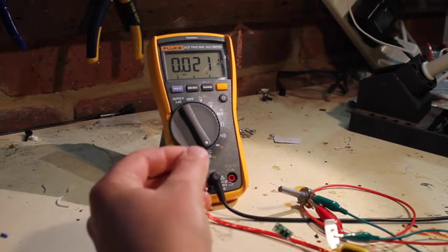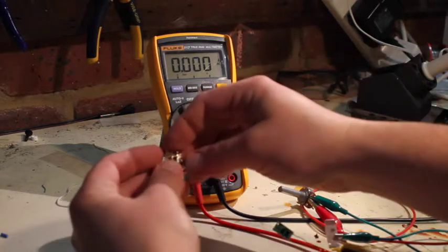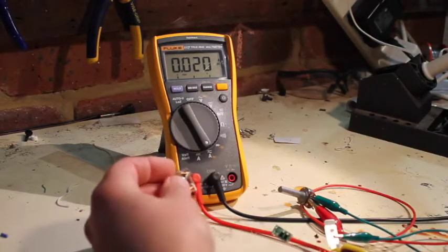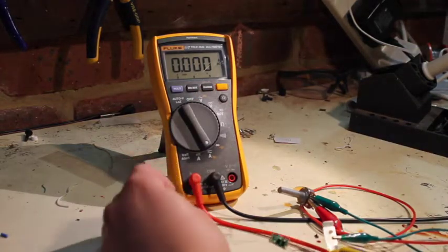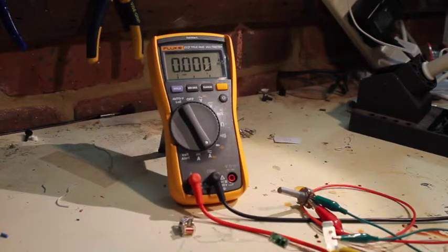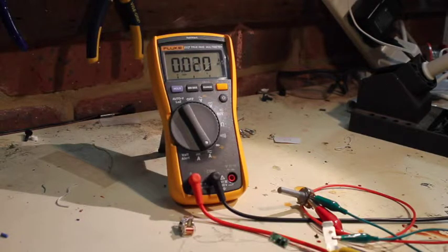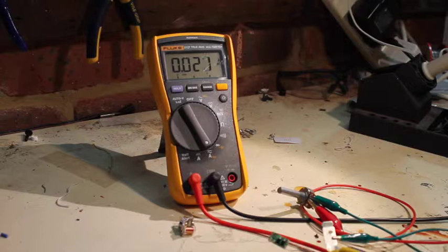What should happen is this should get to 30 milliamps and this solenoid device should activate, that should fire, and we should be able to measure how much current it takes to trip. This thing's designed to trip out at 30 milliamps so let's see what it does.